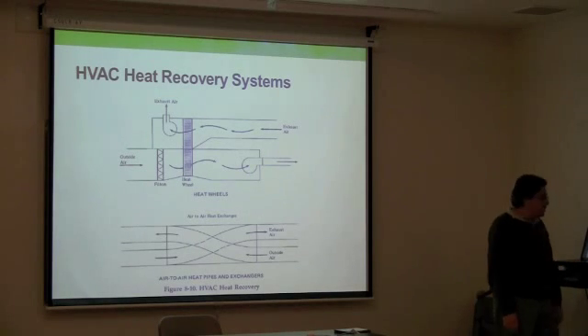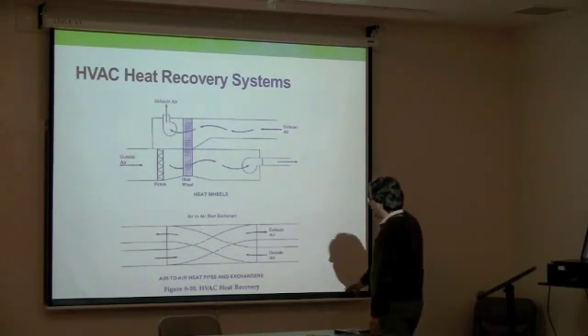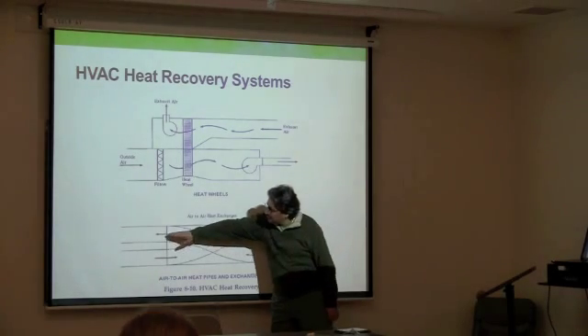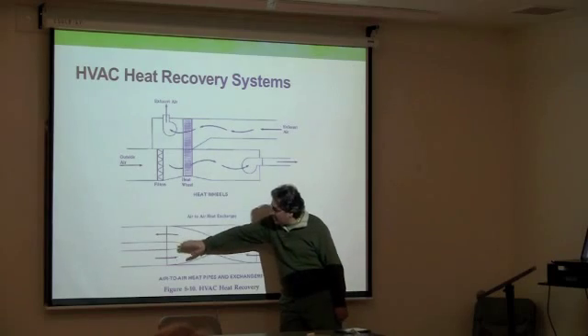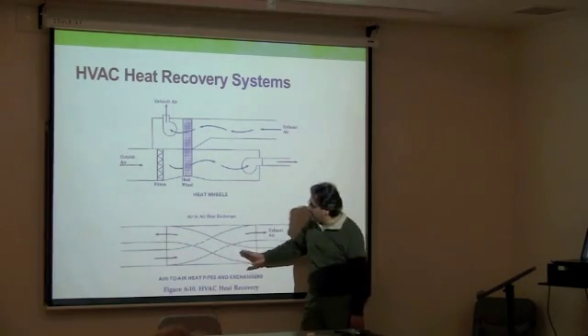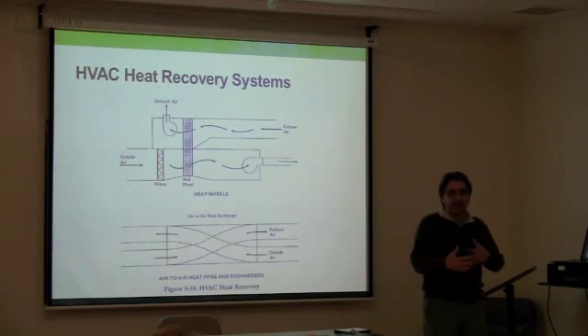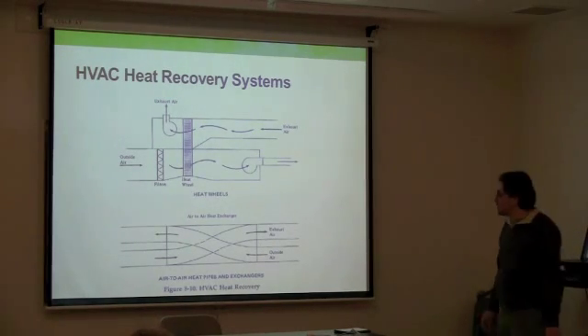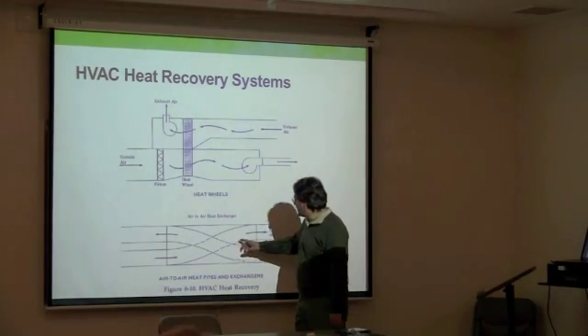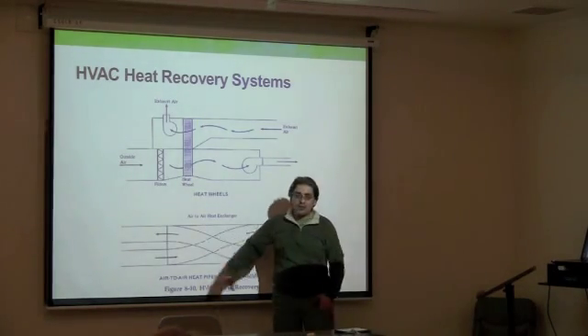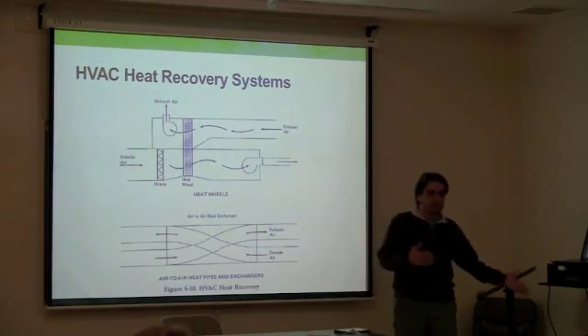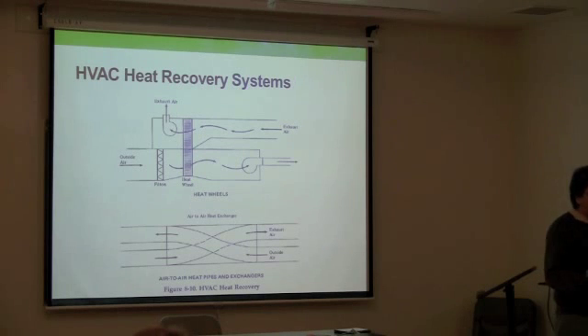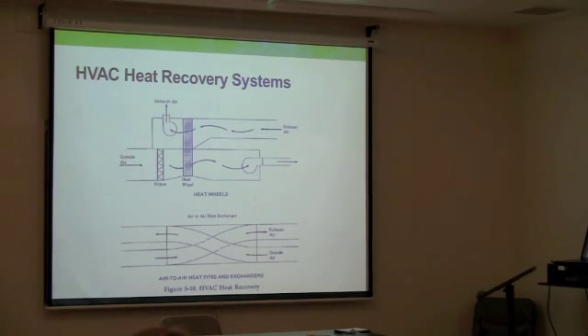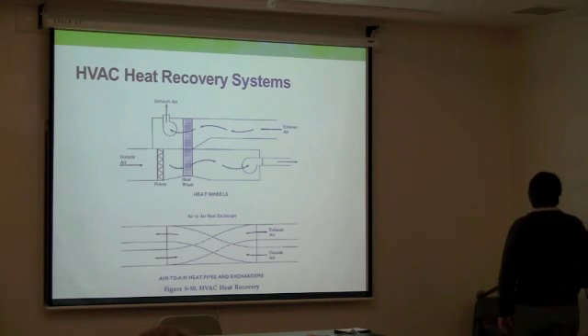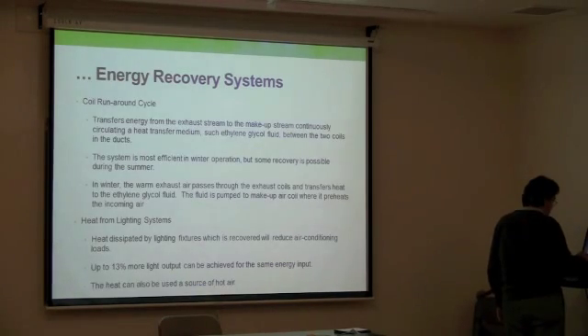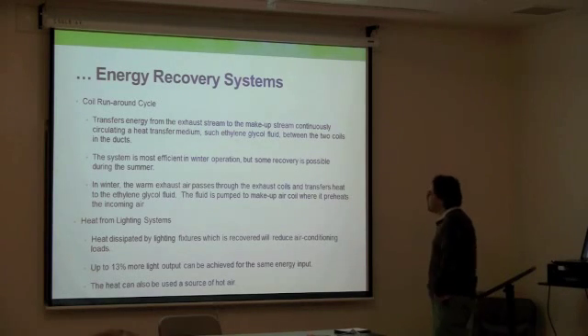And some of them look like this. For example, I have air this way, passage of air this way, a passage of hot air that way. This is a cold air. They basically cross each other at some point, and they mix together, or they transfer heat on some surfaces like the heat exchanger. And what happens is this air becomes cooler, this air becomes hot, right? So you have a hot area, you have a cold area, you can somehow transfer the heat between them by using a heat exchanger. Perfect, try to do that instead of buying the boiler or increasing the capacity of your boiler. So you've got to look at all of the possibility of energy recovery system.